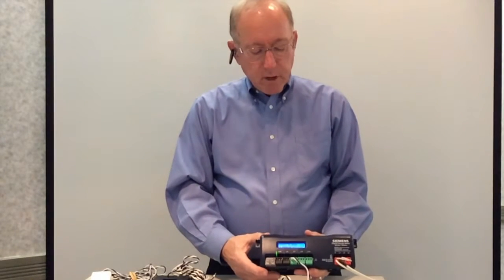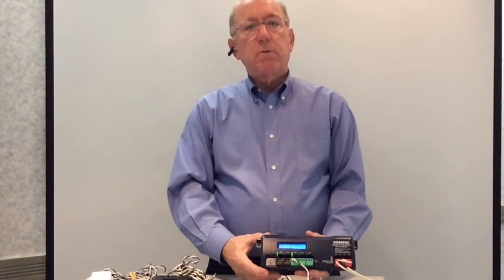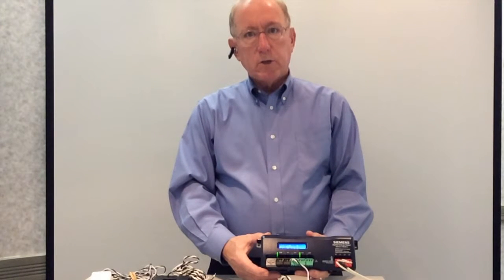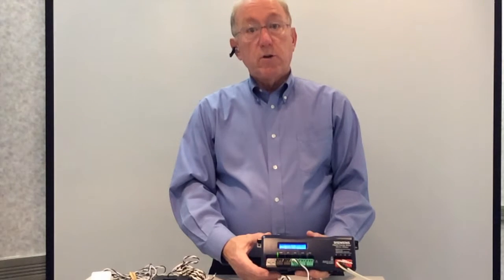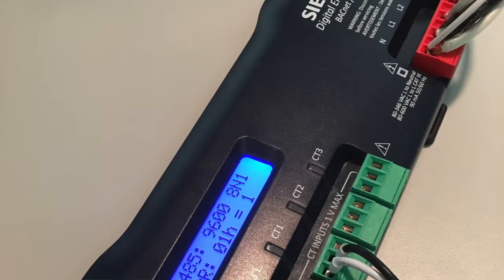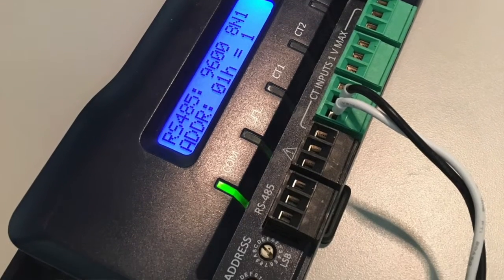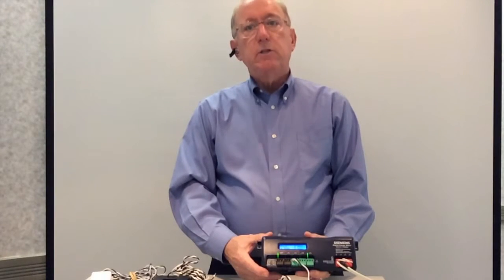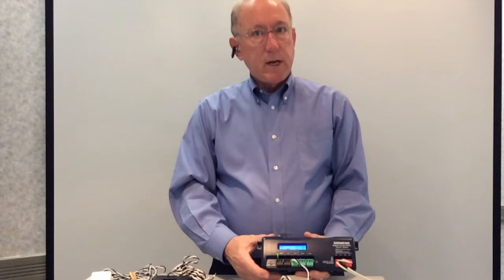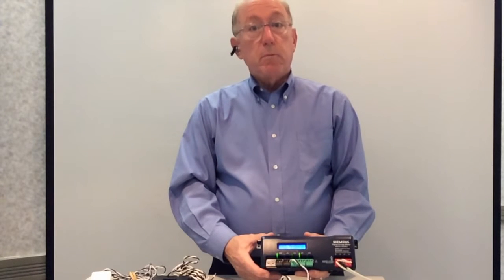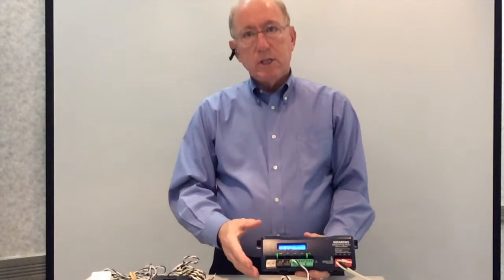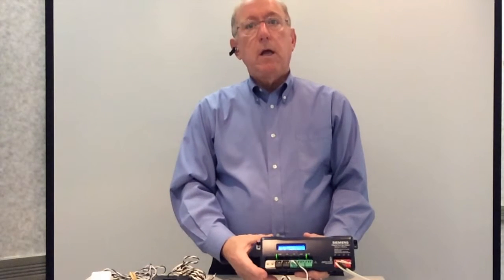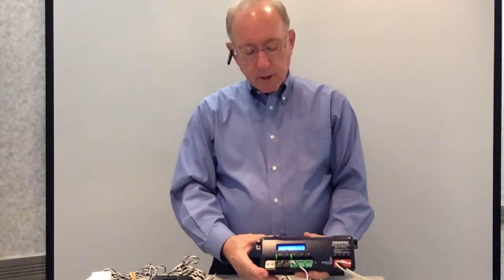This new meter is a very powerful meter. It can measure from single phase to three-phase circuits from 80 to 600 volts AC, covering the Canadian markets also. It's got the ability to handle multiple different types of CT ranges from 50 amps up through 4,000 amps. And Siemens sells these as a metering kit of the meter plus 3 CTs, allowing the meter to be set up and configured to the particularly ordered CT before delivery to the field site to eliminate field setup activities.